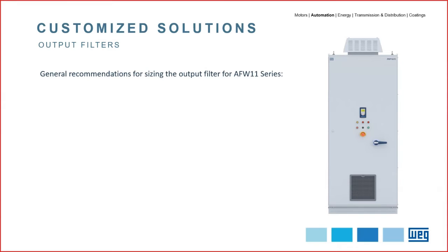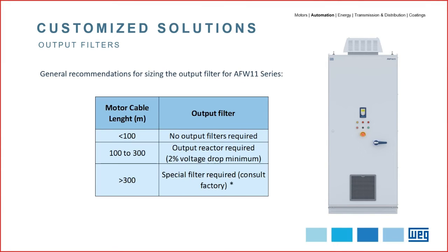Based on several practical cases, some typical distance values are recommended by our engineering team for the CFW11 series output filters. As already mentioned, for a cable length less than 100 meters, no output filter is required. For applications where the cable distances from the VSD to the motors are from 100 to 300 meters, the recommendation is to install an output reactor. For cable distances from 300 meters, a special filter is required. In these cases, WEG's team is available to analyze and recommend the best special filter for each scenario. The available options are dV/dt and sinusoidal output filters.